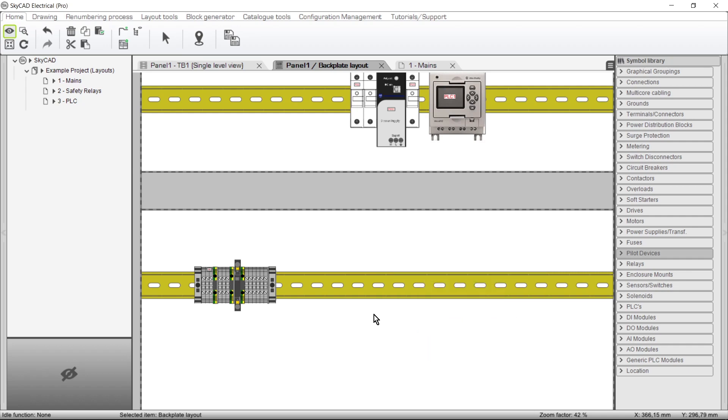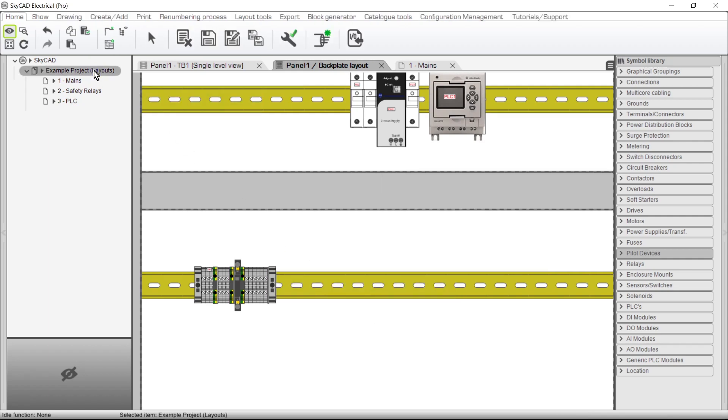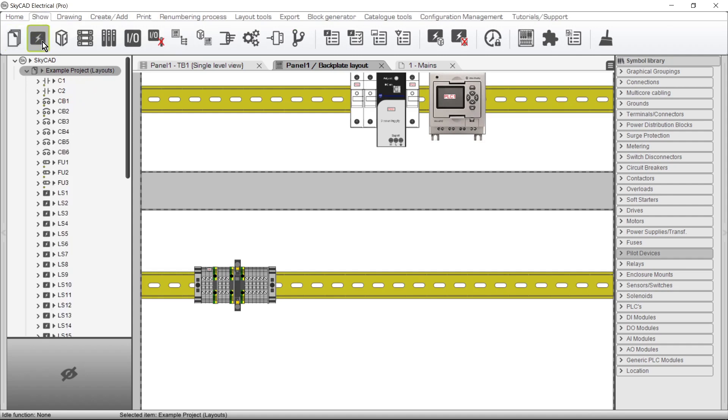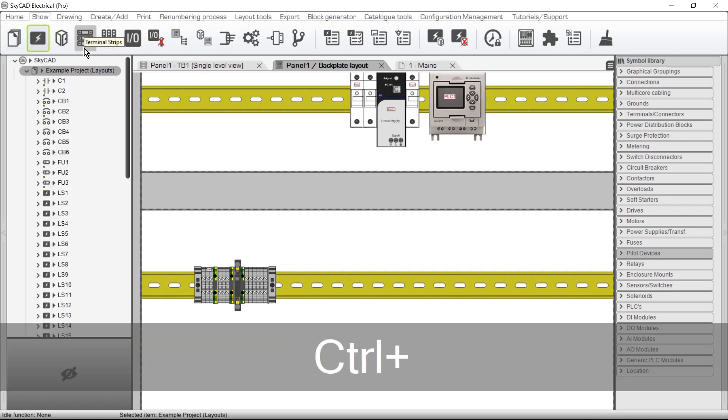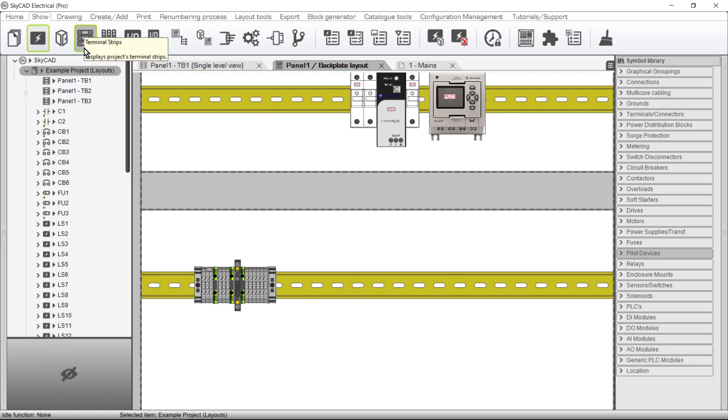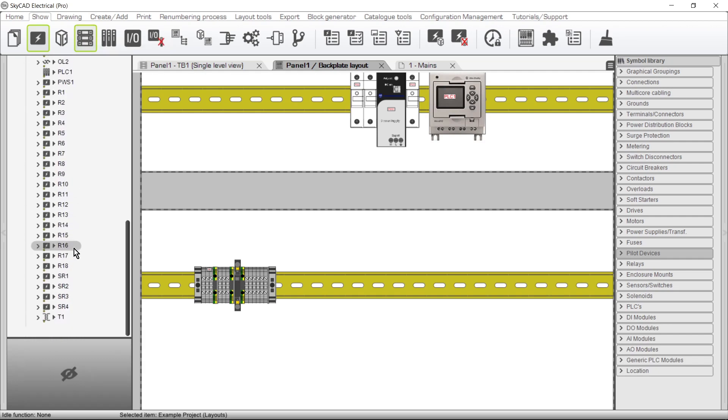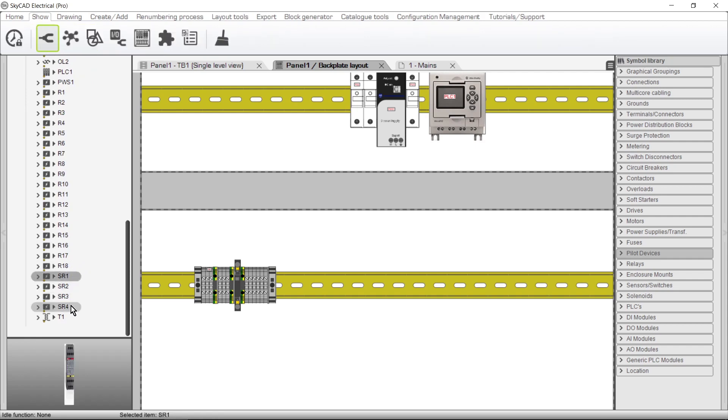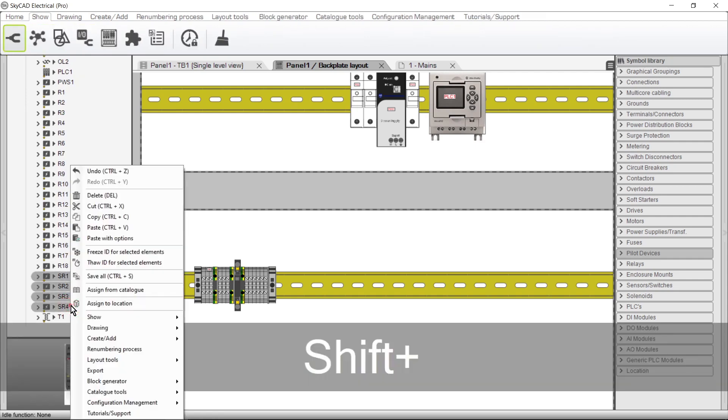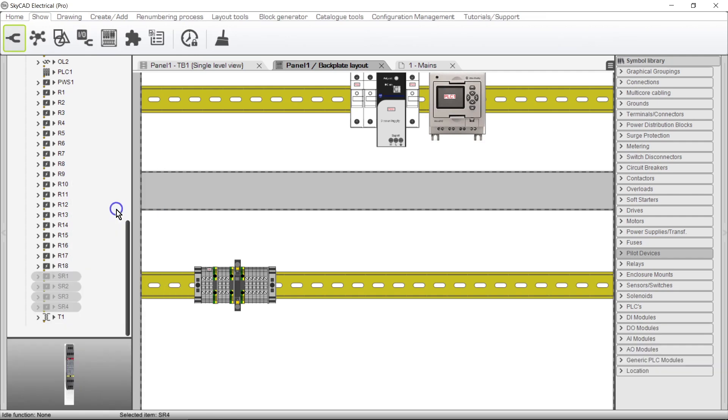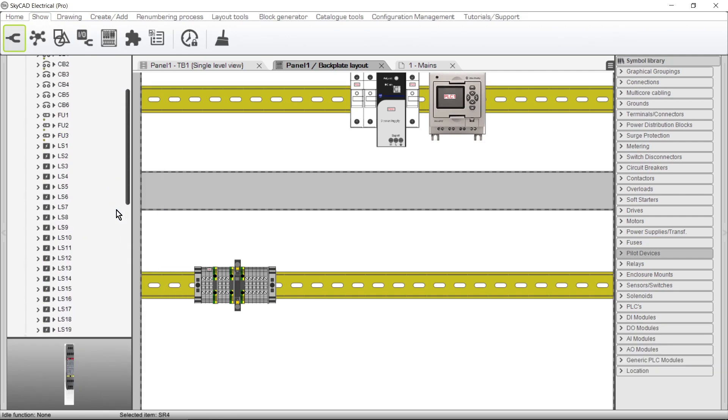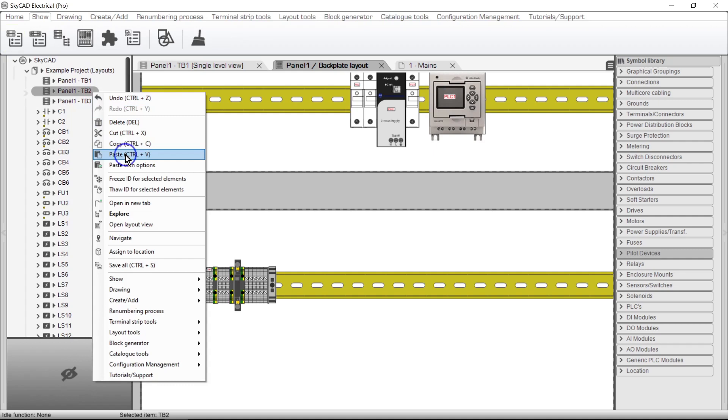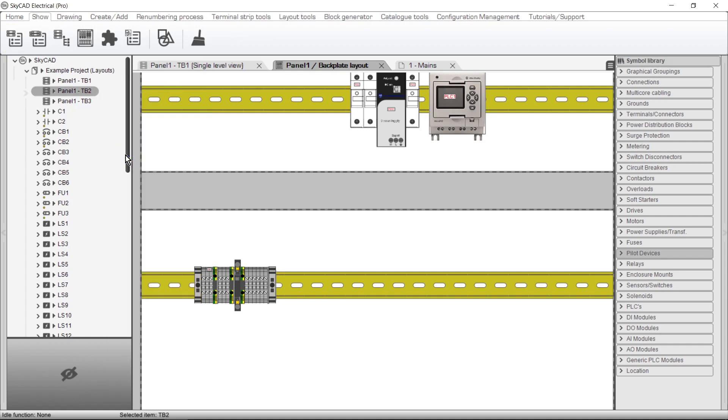This is how to add any component to your Terminal Strip. Select the project in the Tree View, go to the Show tab, and select Components, and while holding the Ctrl key, select Terminal Strips. This shows all the components and Terminal Strips for the project in the Tree View. Now select the components you want to add to a Terminal Strip, right-click, and choose Cut. Then right-click on the Terminal Strip you want to add the components to, and choose Paste. Nothing seems to have changed, but the components have indeed been added to the Terminal Strip.